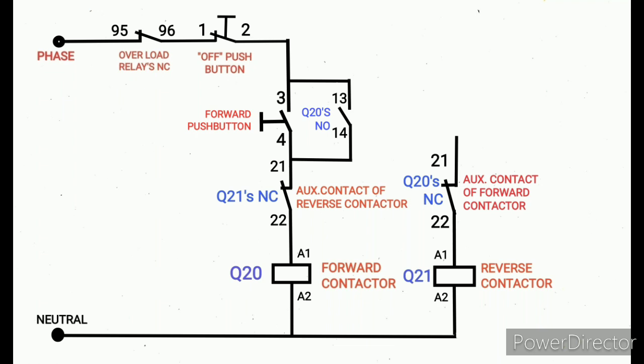If you release the button, it automatically turns off, so we need the hold on. This hold on is Q20's NO, Q20 forward contactor's auxiliary contact 13 and 14.